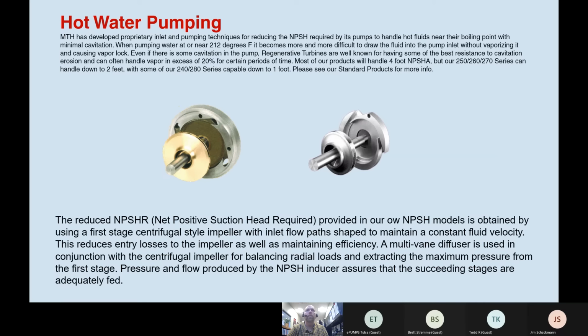And so anyway, that's just to show that there are other types of pumps besides the multi-stage centrifugals that we can replace. And we were talking about the low NPSH. A normal regen turbine pump will run at about 4 to 8 feet on a large scale. Our little close coupled pumps will run at about 1 to 2 feet, maybe even a half a foot on our really small ones, on our T31s.